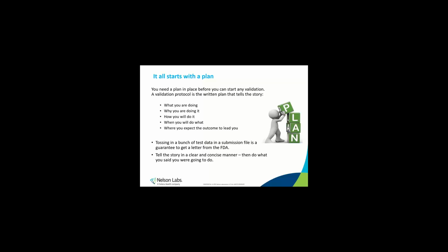It all starts with a plan, or at least it should. If you don't have a plan in place, then how will you know what you're doing and if you're successful at doing it? The validation protocol is the written plan that tells the story of your validation. You remember the lessons from elementary school about good storytelling? You start by asking the 5 W questions of what, where, why, when, and how, and then you write it down. For a packaging validation, you need to say what you're doing, why you're doing it, and the why is usually the most important part. How you will do it, when you will do what, and where you expect the outcome to lead you. In this case, you expect to meet all your acceptance criteria and successfully demonstrate that your sterile barrier system is effective until the point of use.